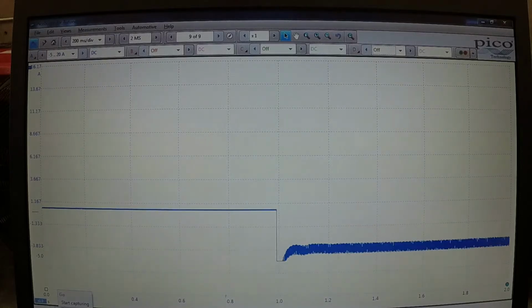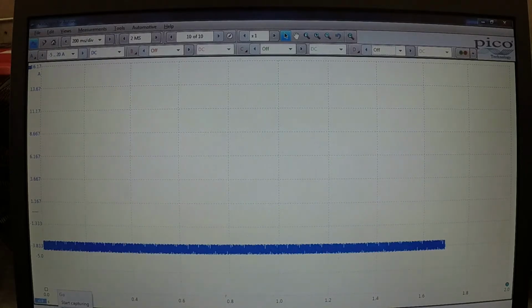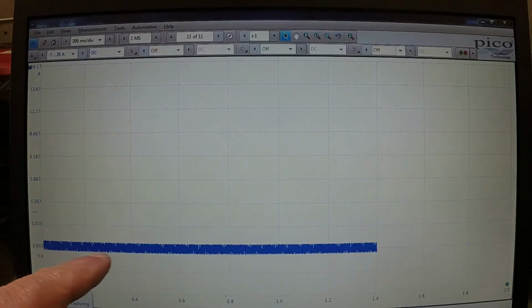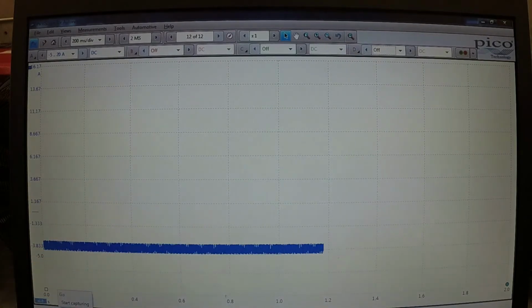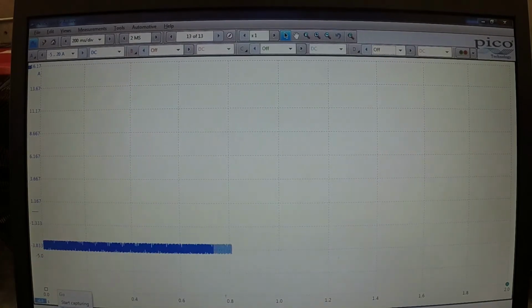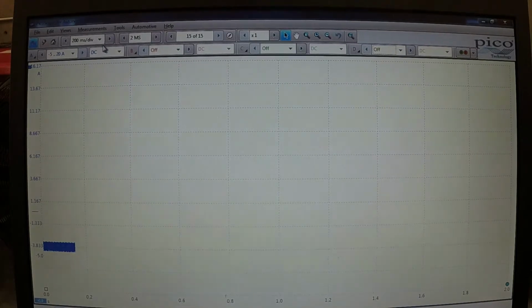Now I can come down here to the very bottom and start my trace, so I'll hit Start Capture, and turn on the tool on the amp clamp. Now if you see that, it's reading the amp clamp, but it's not doing a very good job of reading it, so we can come up here and adjust our milliseconds per division.